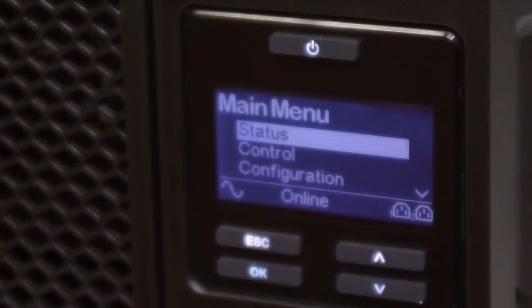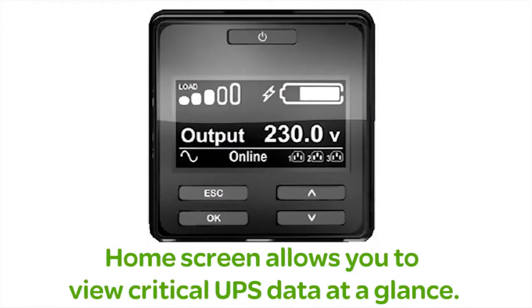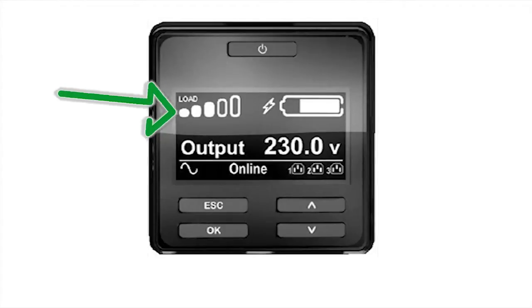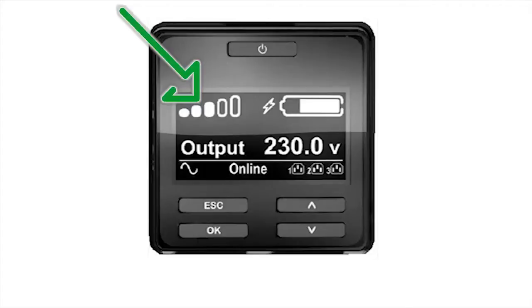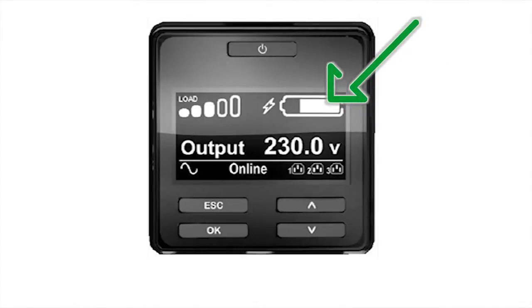Users can change any of the selected options once they've exited the setup wizard. The LCD status screen displays a wealth of valuable information. The load indicator displays present UPS load in relation to overall UPS capacity. The approximate load capacity percentage is indicated by the number of load bar sections illuminated — each bar represents 20% of the load capacity. The battery charge icon shows the state of battery charge in relation to overall battery capacity, indicated by the amount of the battery bar that is illuminated.